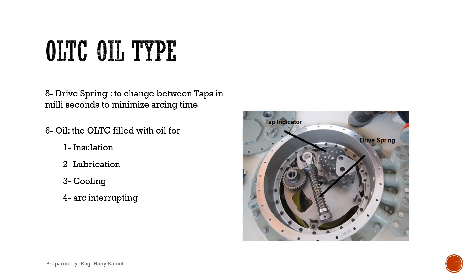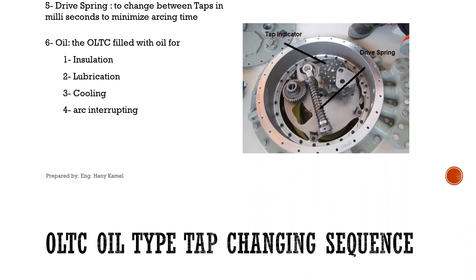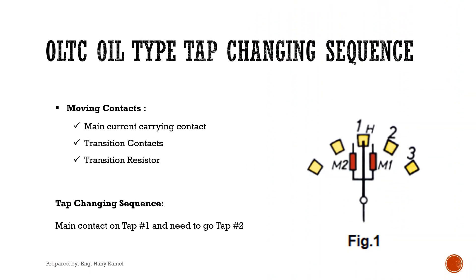Oil is used in the OLTC for: insulation medium; lubrication for the moving parts inside the tap changer compartment; cooling for the tap changer; and arc interruption facility during tap changing. Moving contacts include: main current carrying contacts; two transition contacts, which help in the make-before-break sequence; and a transition resistor, which limits the short circuit current during shorting of taps in the tap changing sequence.